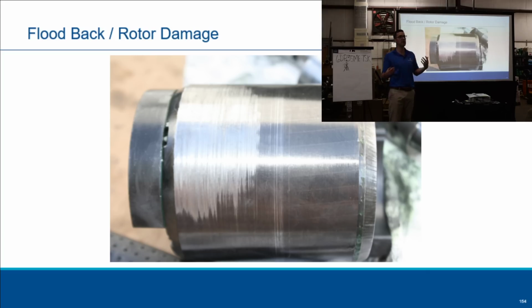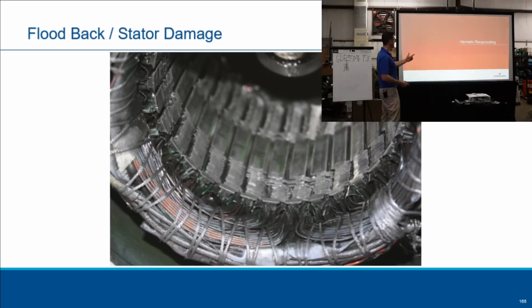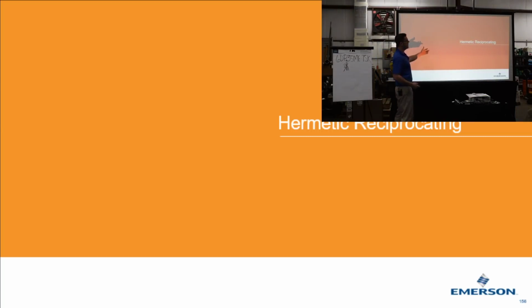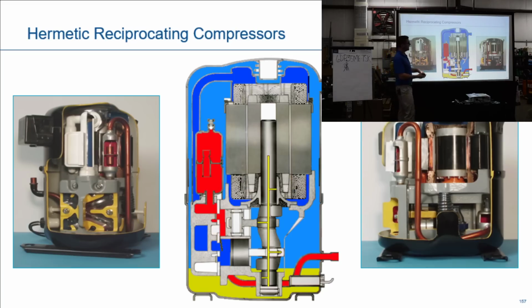Because if you don't pull it apart and you just pull it out and put it back in, you don't check, or don't notice it, because floodback could happen at any time, maybe after a defrost. So you set up your superheat and everything's great, but you have a defrost and then maybe that's when it happens, right? Okay, stator failure. Okay, hermetic reciprocating, same thing. That refrigerant, you're getting floodback, comes in and it starts to suck up liquid refrigerant, washing out the bearings again, which leads to another failed compressor.